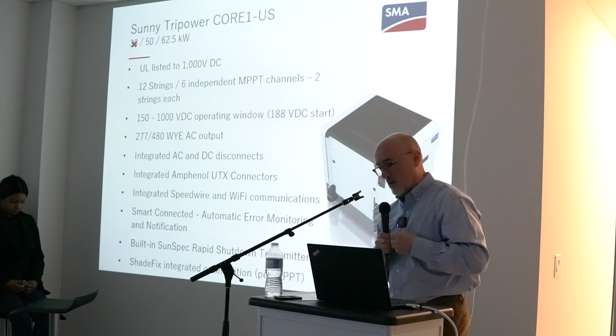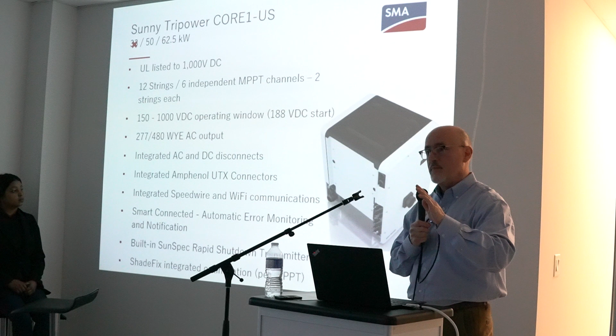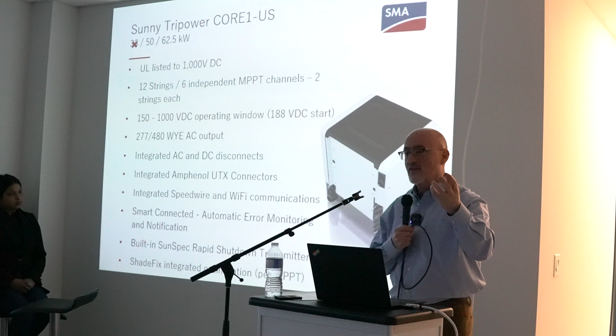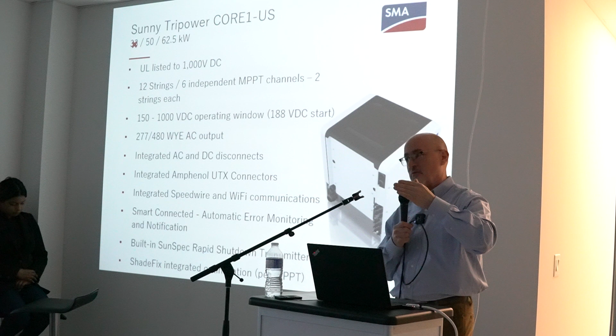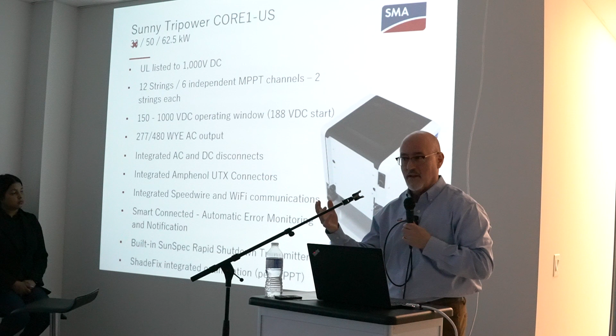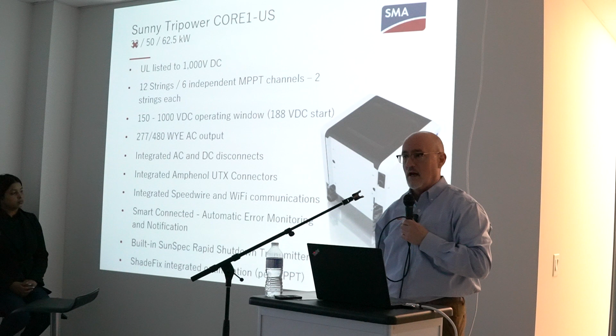I also heard Alex mention in his last presentation, in the US, well, let me back up. In Canada, as long as you put the inverter within a meter of the array boundary, you don't need module level rapid shutdown. That was the case in the US up until the National Electric Code Cycle 2017. So up until this point, we've had to put module level rapid shutdown devices, which add a lot of expense and failure points, additional connections, which is a big problem.